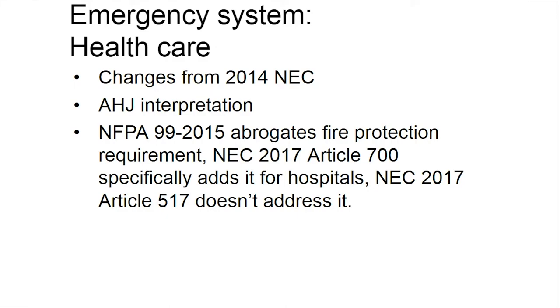Now, the handbook is not enforceable as code, but its provisions carry a lot of weight with AHJs, so it's certainly likely that a requirement for additional fire protection above ceilings would be enforced. The 2015 edition of NFPA 99, that's the healthcare facilities code, specifically says that those fire protection requirements don't apply to healthcare facilities. That exemption, though, did not appear in the 2017 edition of the NEC, Article 517, which also covers healthcare requirements. And instead of abrogating the requirement for healthcare, hospitals were specifically added to the occupancy list that requires that fire protection. So it is not clear that the exemption from NFPA 99-2015 will ever have any effect. It looks as though we're going to see the requirement for fire protection enforced on hospitals.